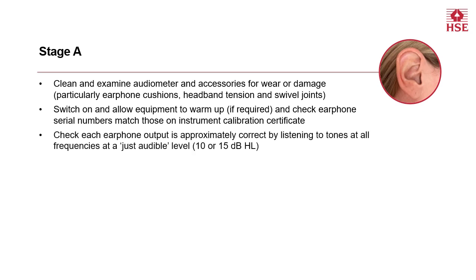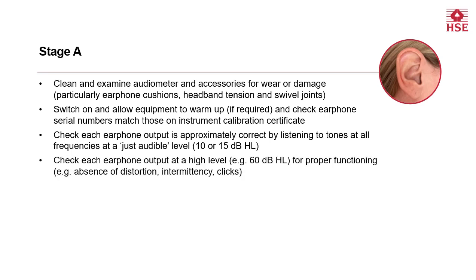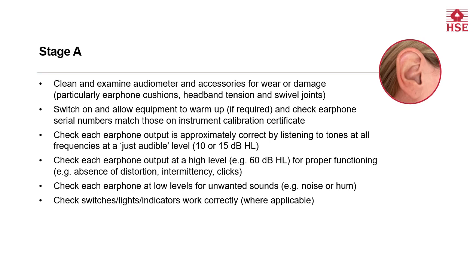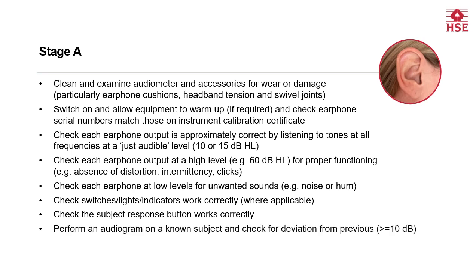Then check each earphone output is approximately correct by listening to the test tones at all frequencies at a just audible level. Check each earphone output at a high level for proper functioning, that is, the absence of distortion, intermittency and clicks. Check each earphone at low levels for unwanted sounds such as noise or hum. Check switches, lights and indicators work correctly where applicable. Check the response button works correctly. And at least weekly, perform an audiogram on a known subject to check for deviation from a previous audiogram.